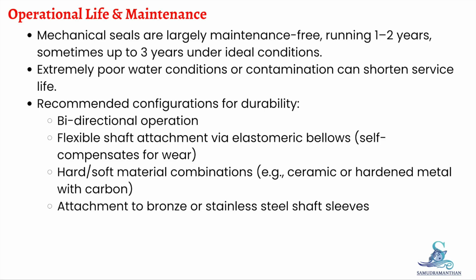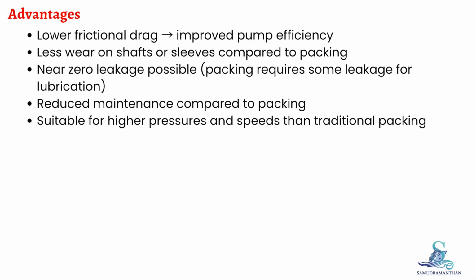Advantages: lower frictional drag, improved pump efficiency, minimal wear on shafts or sleeves compared to packing, near zero leakage, unlike packing, which requires some leakage for lubrication, reduced maintenance requirements, can be applied to higher pressures and speeds than traditional packing.